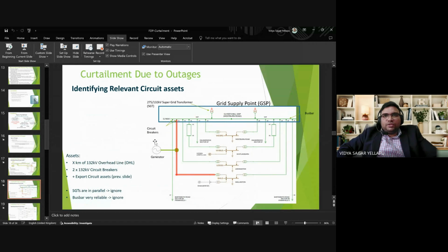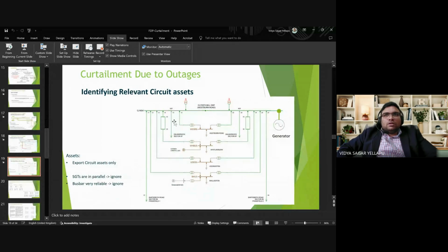This is another scenario in which the generator is connected to the circuit that is directly leading to the substation, and the other part of this circuit is getting connected somewhere here. So if there is maintenance here in the circuit, then it is to be curtailed. Coming to outages in the SGTs, those are in parallel, so those are anyway loaded to the n-1 capacity, so those are not accounted for. The failure rates of these bus bars and their planned maintenance are very rare, and if those are to be there, those are done along with the maintenance of these transformers, so no additional curtailment is added. This is another scenario in which a generator will be curtailed. Here, the generator is directly connected, so it is constrained by this export cable only.